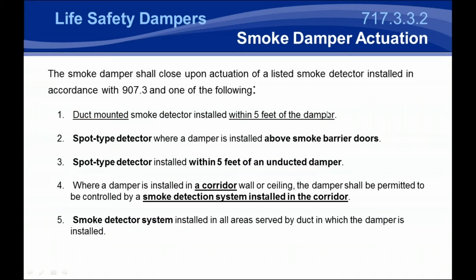For smoke damper actuation, of course, as fire damper manufacturers, we'd love to sell you smoke dampers, but we typically recommend that you use the most cost-effective, the least cost option out there. One of the problems with fire damper manufacturers supplying smoke detectors, especially smoke detectors that are mounted in a damper, is they're not going to be addressable. There are a lot of smoke detectors out there, and most of them are not addressable for the fire alarm system or the building control system.